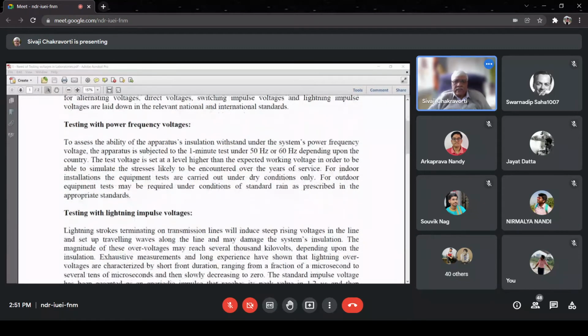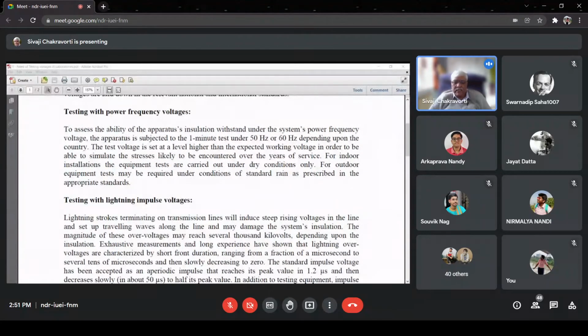Now, when I say testing with high voltages, you should immediately ask me, what are you talking about? Voltage doesn't make any sense on its own. I have to specify what type of voltage. When I say type of voltage, basically I am talking about the waveform. The most common waveform available in our power system is the 50 hertz waveform. We call it the power frequency voltage because 50 hertz is our power frequency. In the entire world there are two power frequencies: one is 50 hertz, the other is 60 hertz. The Indian system is 50 hertz.